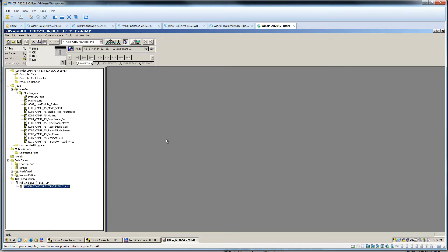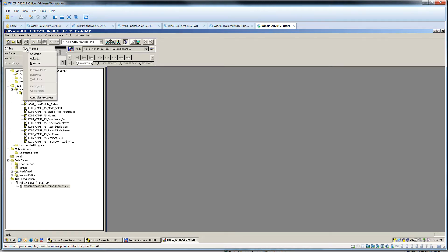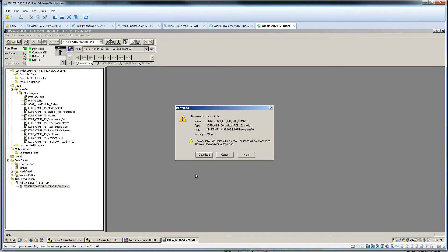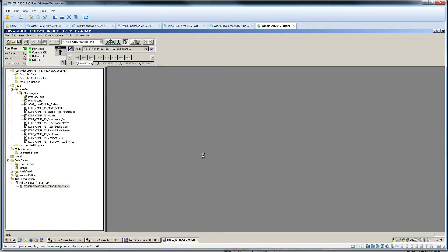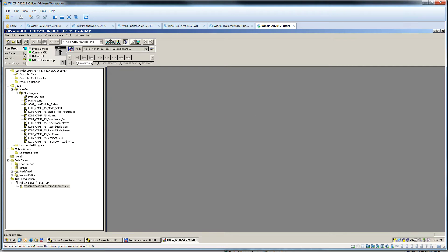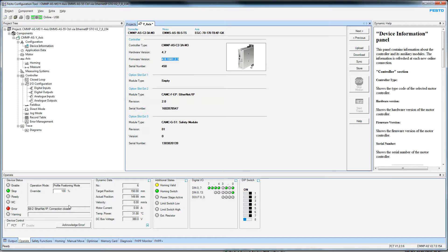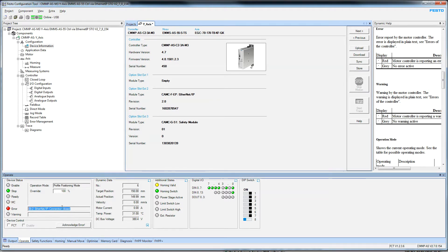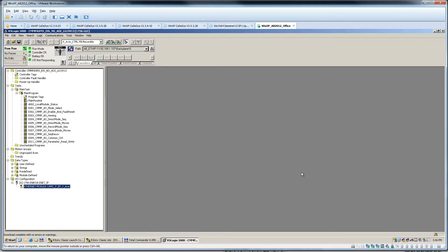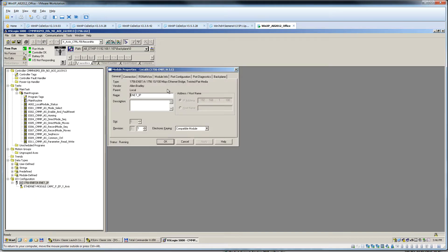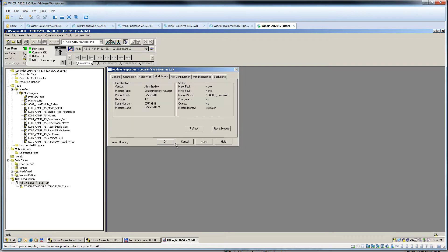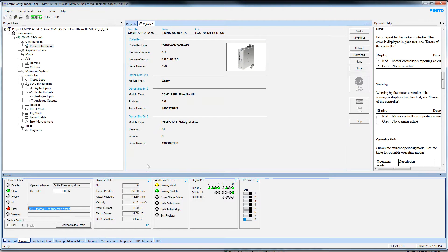I'm going to go online and download. We're online. Right off the bat, you'll see we've got an Ethernet connection. This is the only real big problem I have found. The card, the module itself needs to be 4.8. I have not tested anything newer, but I know some older things don't work and cause the Ethernet IP to continuously drop out and get faults.